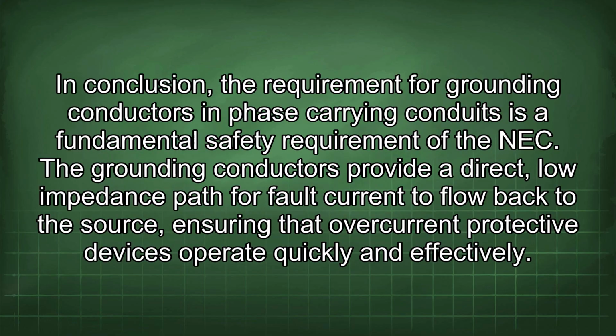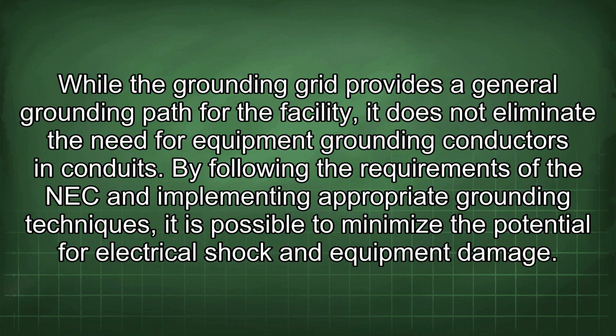In conclusion, the requirement for grounding conductors in phase-carrying conduits is a fundamental safety requirement of the NEC. The grounding conductors provide a direct, low-impedance path for fault current to flow back to the source, ensuring that overcurrent protective devices operate quickly and effectively. While the grounding grid provides a general grounding path for the facility, it does not eliminate the need for equipment grounding conductors in conduits. By following the requirements of the NEC and implementing appropriate grounding techniques, it is possible to minimize the potential for electrical shock and equipment damage.